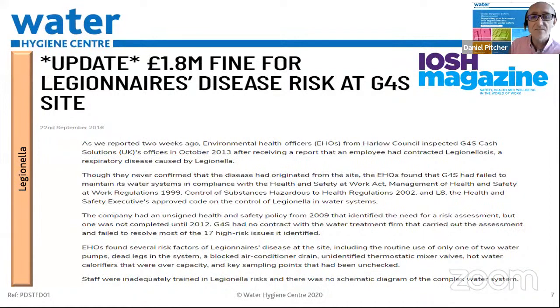There were dead legs identified within the systems that hadn't been resolved. The location of TMVs, thermostatic mixing valves, were unknown around the building. The domestic hot water storage was oversized, and sampling points were unchecked.